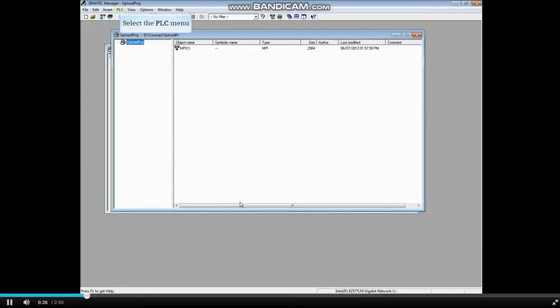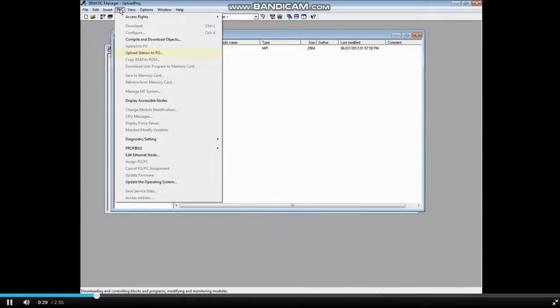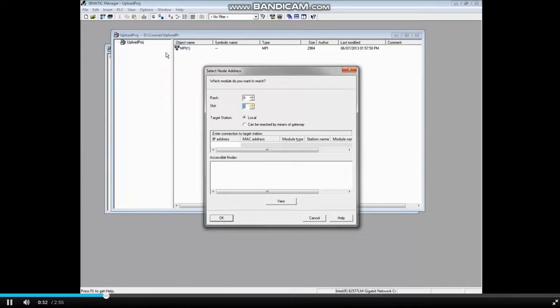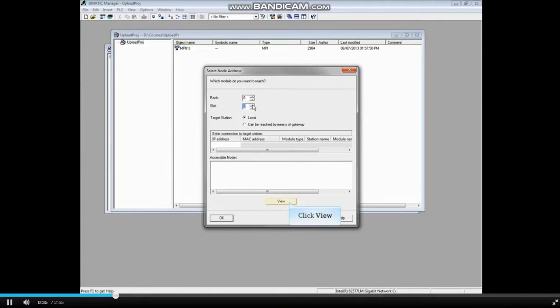With the project level highlighted, select the PLC menu. Choose Upload Station to PG. Choose Slot 2 for the PLC. Click View to pull the accessible nodes.